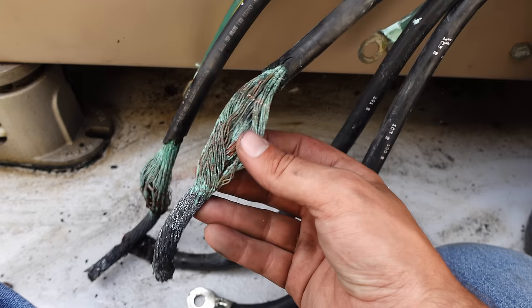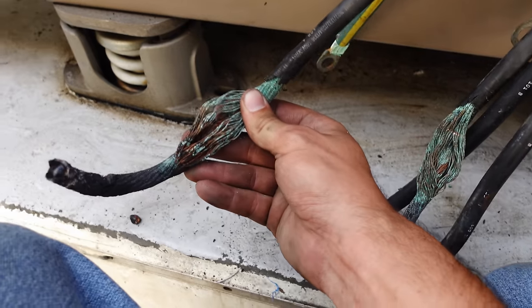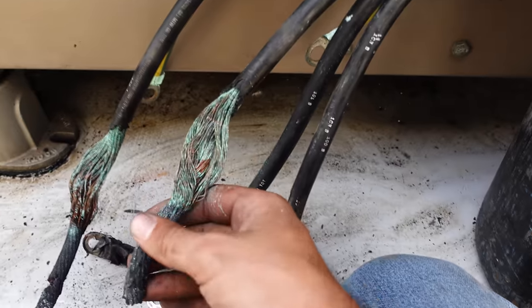When we were troubleshooting this compressor, I didn't have a reason at the time to open the peckerhead and actually look at this wiring. I kind of wish I had at this point — this was definitely contributing to our current issues. For those snickering: yes, these are referred to as an actual peckerhead. It's not referring to male genitalia — it is just what we call it. I couldn't tell you where that term comes from, but that's what it's called.